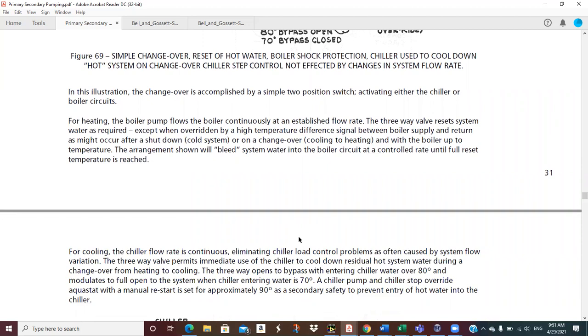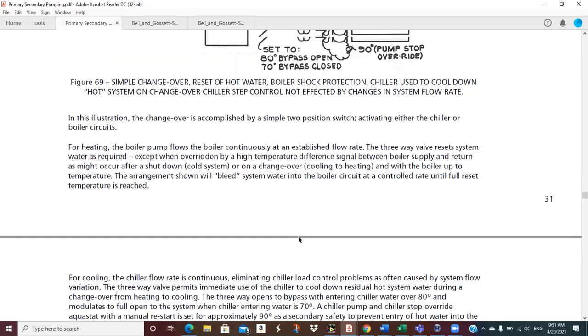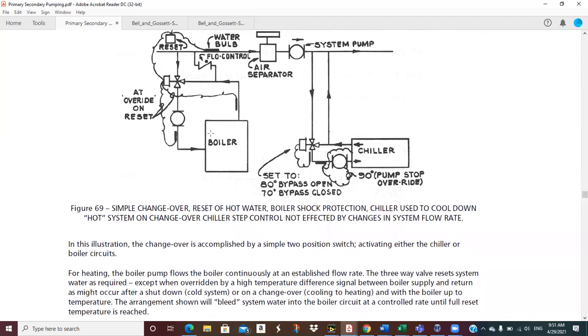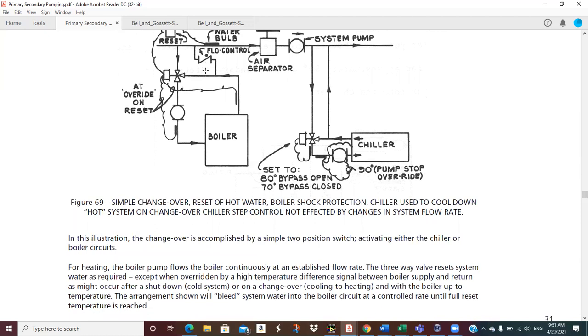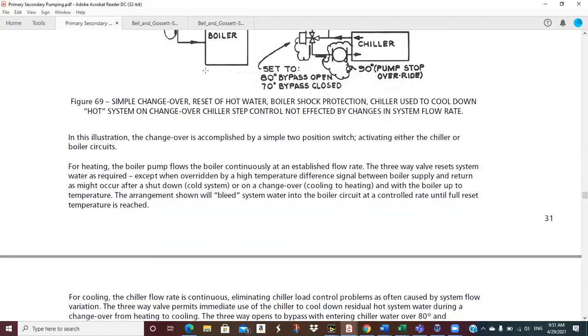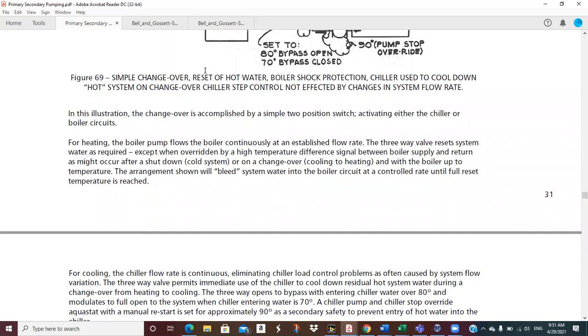For heating, the boiler pump flows the boiler continuously at an established flow rate. So I'm going to run this boiler pump all the time, but it may be going around in a circle. It depends on the action of this control valve, whether I'm letting any of my system water back through to actually get heated up, to put some cold water back in here so the boiler will fire. You know, if I just circulate that loop and it's hot, then the boiler controls will just shut down the flame and it'll just sit there until it senses a water temperature drop. So let's see, the three-way valve, let's see if I can get all this up here.